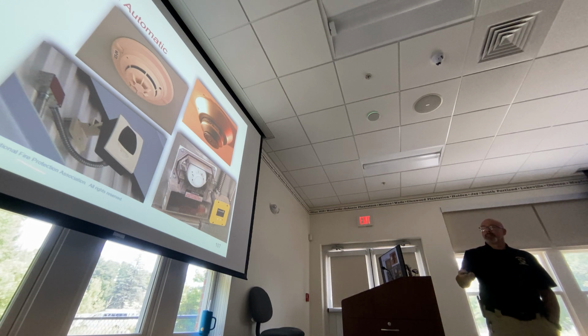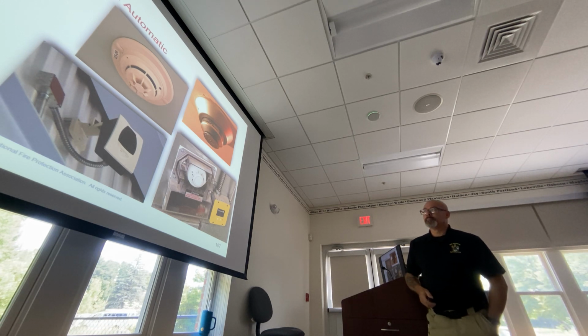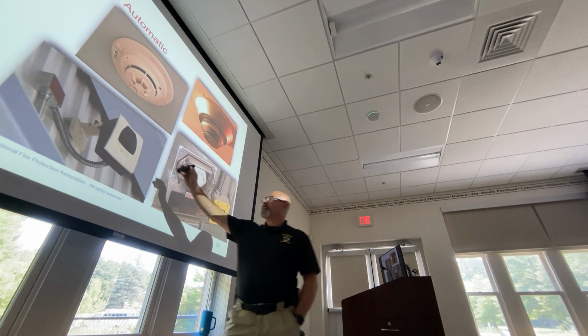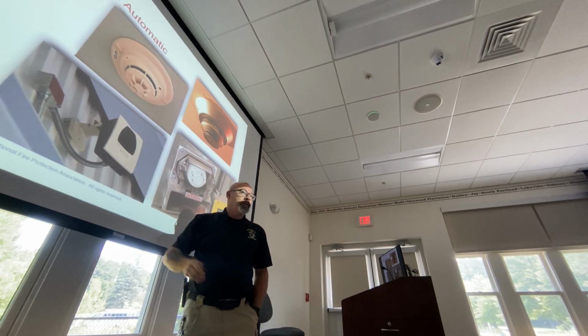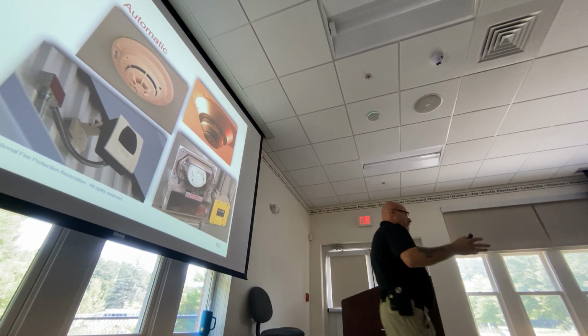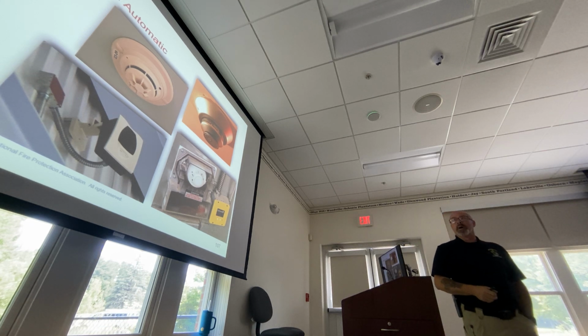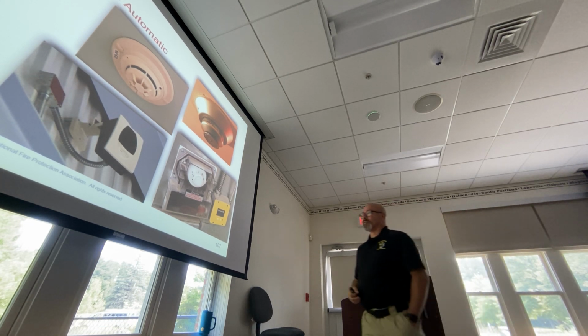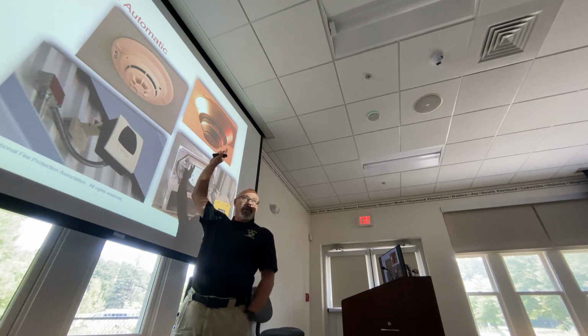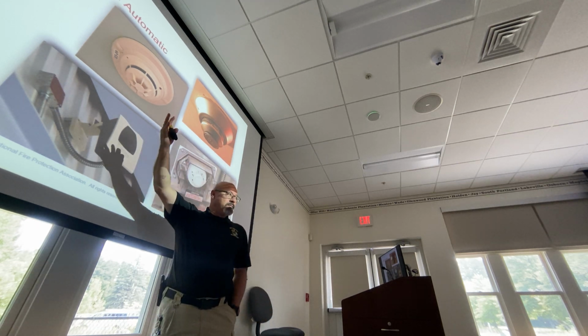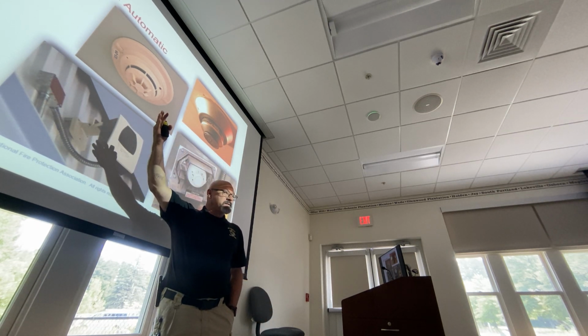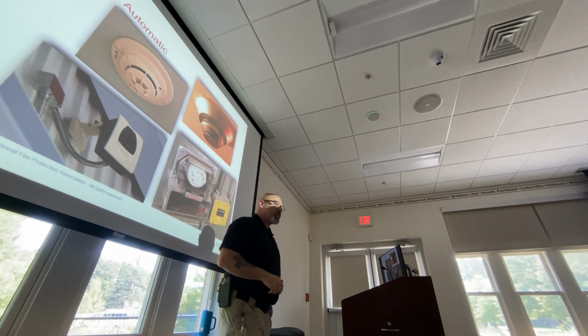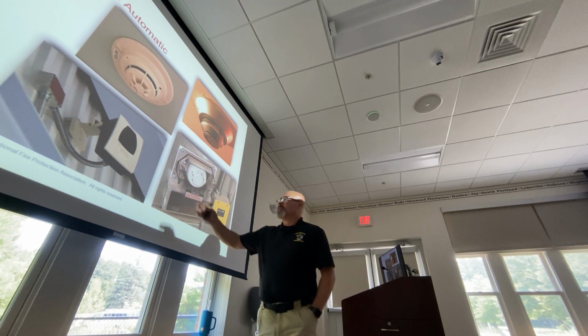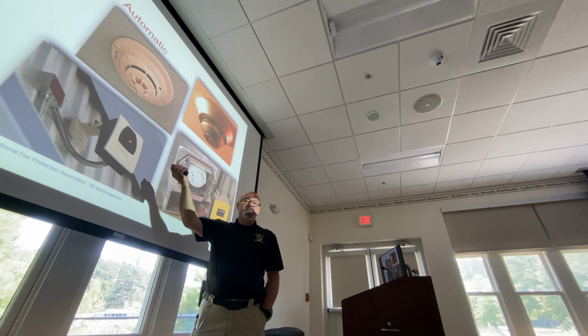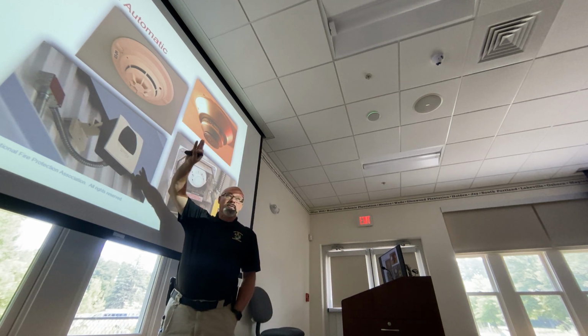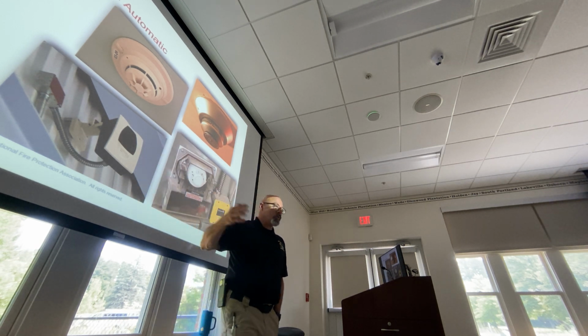What's this one? Is that an infrared? Can't see it. Photo eye. Either it's a laser or, yes, a photo eye type scenario. Kind of like your garage door has a receiver on the other side. You try to close your door and you walk past this, the door goes back up. Same scenario. It always has that beam. You break the beam with smoke, it will go into alarm.